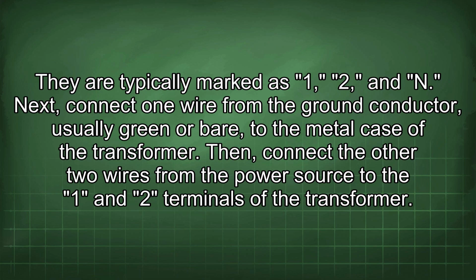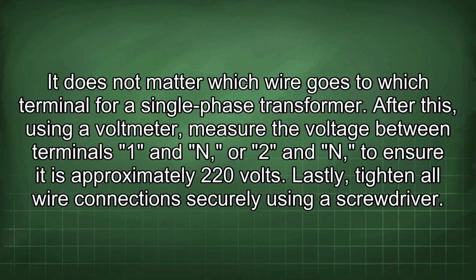Next, connect one wire from the ground conductor, usually green or bare, to the metal case of the transformer. Then, connect the other two wires from the power source to the 1 and 2 terminals of the transformer. It does not matter which wire goes to which terminal for a single-phase transformer.